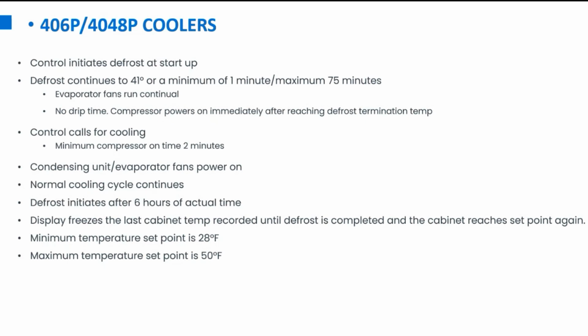The next point here, the third one from the bottom, if you're following along, is kind of the big one. And I'll let Bud explain this one as far as the defrost, how it operates on the display. Yeah, when your control initiates a defrost, it will lock in the last temperature of the cabinet. So let's say our cabinet at 406, we're at 35 degrees when it initiates a defrost.